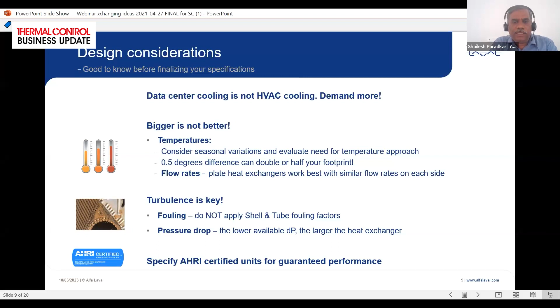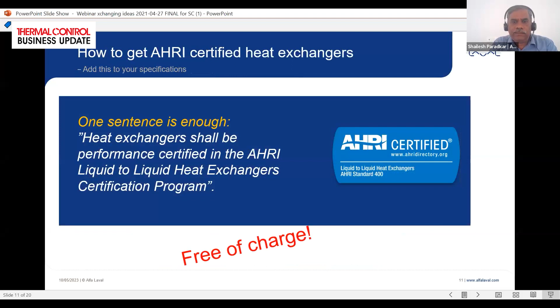Most data centers work with certified equipment like chillers and cooling towers, so we also recommend going with AHRI certified plate heat exchangers for guaranteed performance. It's very simple: you just need to specify that the heat exchanger shall be performance certified under the AHRI liquid to liquid heat exchanger certification program. The good thing is it's free of cost, and Alfa Laval offers a series of AHRI certified heat exchangers.